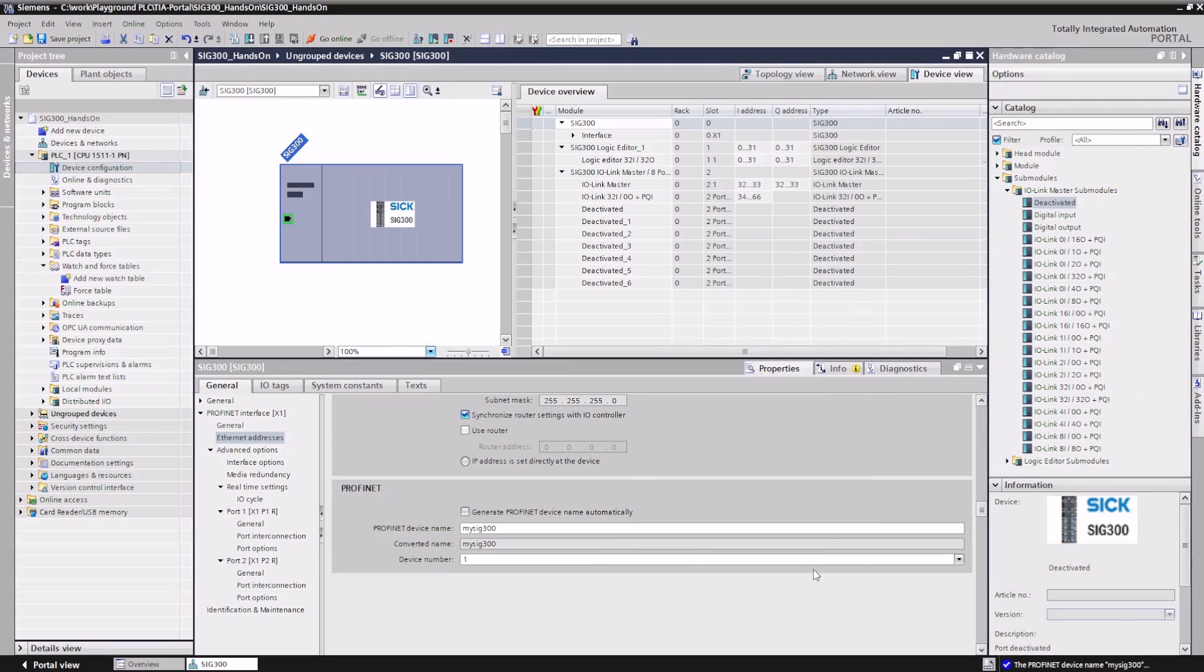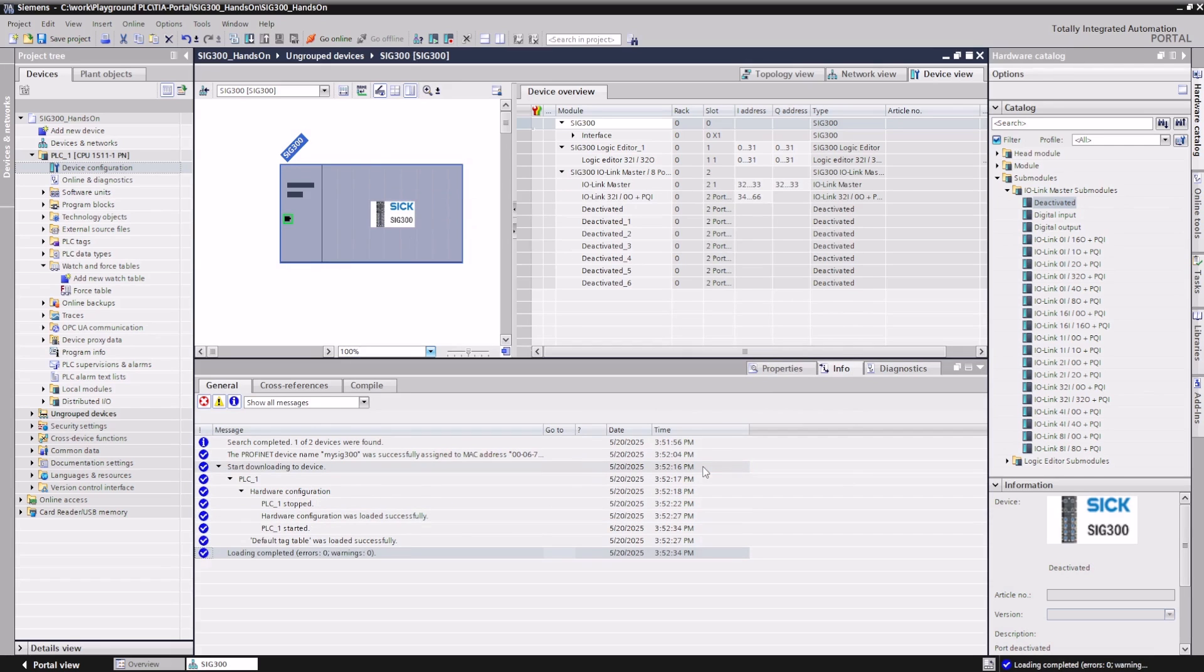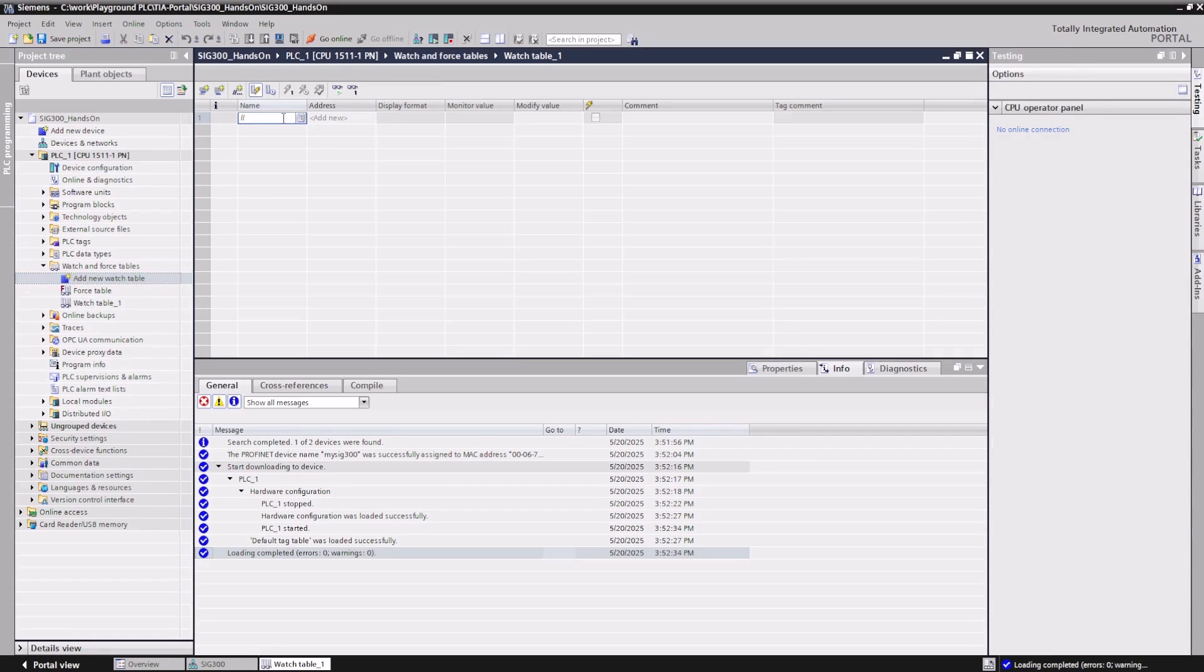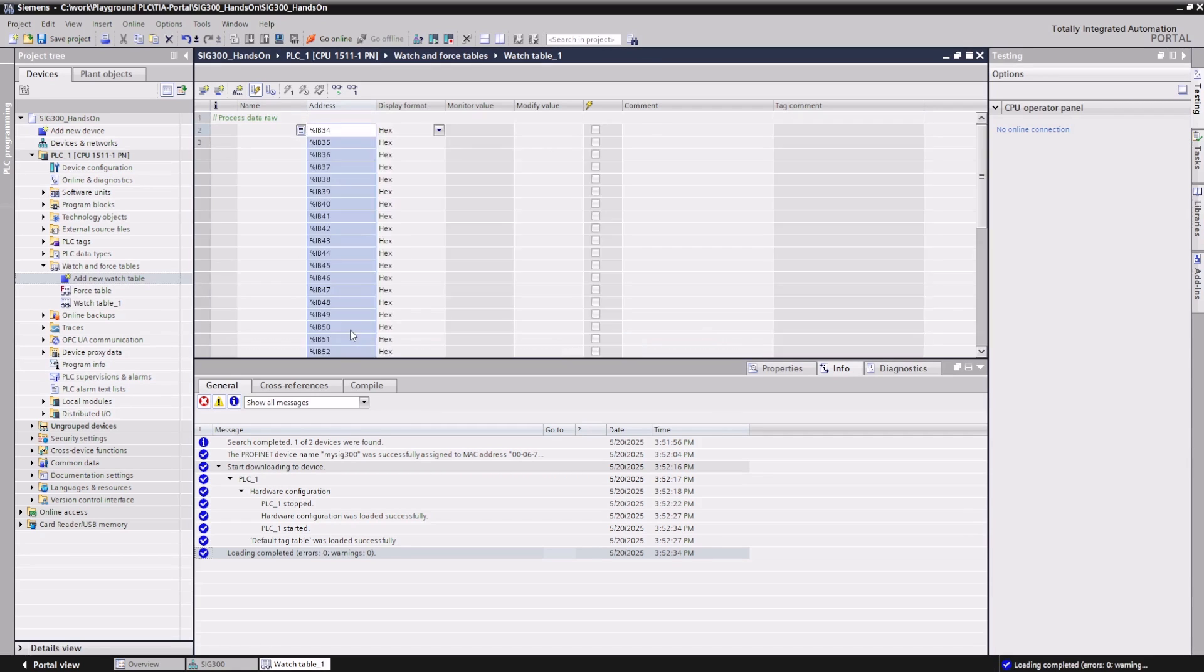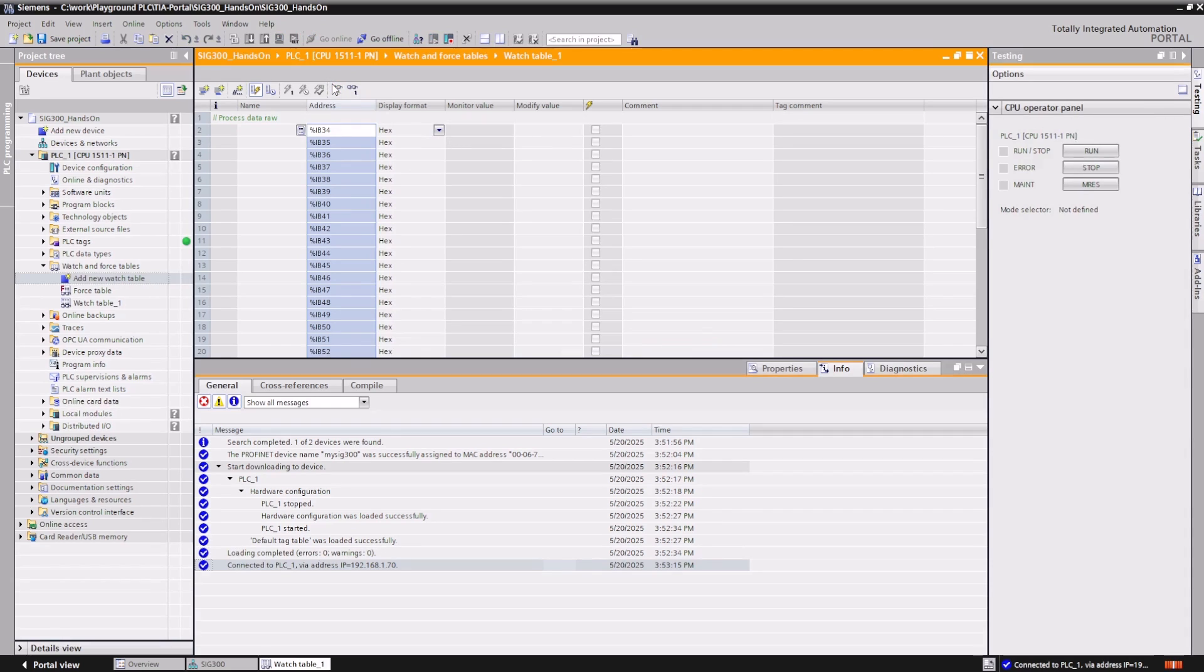Now, download the project to the PLC. The raw data of the MPB10 sensor is accessible using the configured IO addresses. To monitor it, we create a new watch table and add the corresponding input address as a byte representation. The operating instructions describe how to interpret the process data bytes.